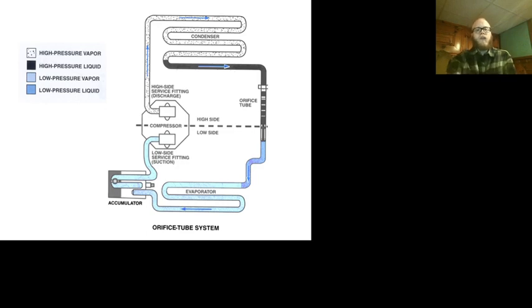But this accumulator here, you can see, again, I don't know why they draw them like this, but it would normally be sitting upright in the vehicle. You can see that the straw here, that is the outlet going into the compressor, is poking up because it's trying to make sure it's only catching vapor and no liquid. The liquid can accumulate down here at the bottom for a little bit, and this is in the engine compartment. So the heat of the engine and the exhaust and all that kind of stuff will help boil off any liquid refrigerant that's inside that unit, because we'll get up to operating temperature sooner or later. There are government mandates on that stuff. So right now I think we're somewhere around the 5 to 7 minutes range from start when a vehicle should be up to temp. So you can see how that goes.